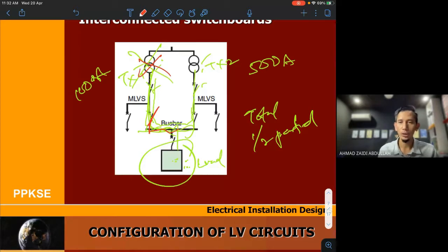But in order to make this load perform or operate, you can use the supply from this transformer 2. So you just open this switch using an automatic transfer switch. So the supply will come from this transformer directly to this load. But since the normal is 1000 amp and this is only 500 amp, this transformer will surely not be able to cover the whole of the load. So you must separate it.